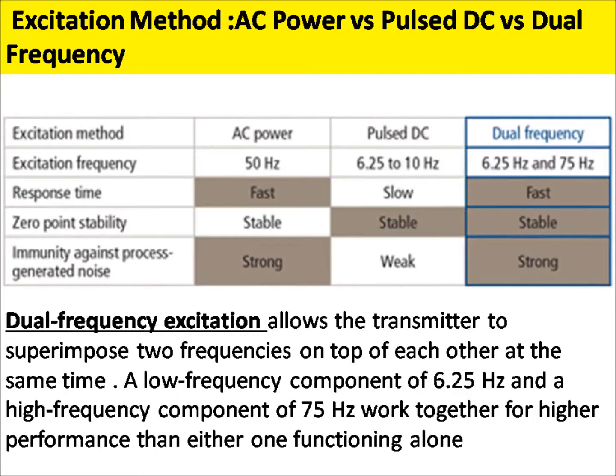This approach works, but as transmitters got smarter, it was possible to incorporate circuitry capable of using both frequencies simultaneously. Dual-frequency excitation allows the transmitter to superimpose two frequencies on top of each other at the same time. A low-frequency component of 6.25 Hz and a high-frequency component of 75 Hz work together for higher performance than either one functioning alone.